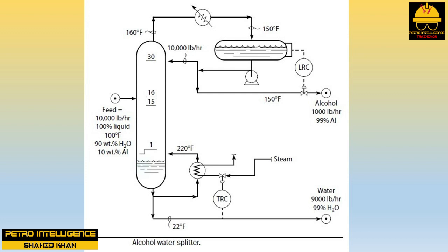This increases both the total tray pressure drop and the height of liquid in the tray's downcomer. Increasing reflux rates with the reboiler on automatic temperature control will always push the tray closer to — or even beyond — the point of incipient flood.